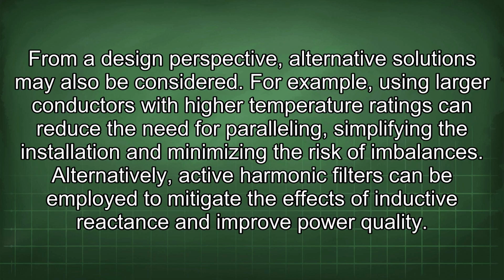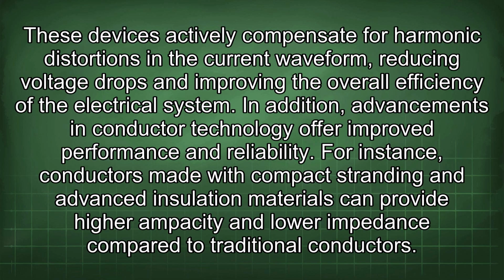From a design perspective, alternative solutions may also be considered. For example, using larger conductors with higher temperature ratings can reduce the need for paralleling, simplifying the installation and minimizing the risk of imbalances. Alternatively, active harmonic filters can be employed to mitigate the effects of inductive reactance and improve power quality. These devices actively compensate for harmonic distortions in the current waveform, reducing voltage drops and improving the overall efficiency of the electrical system.